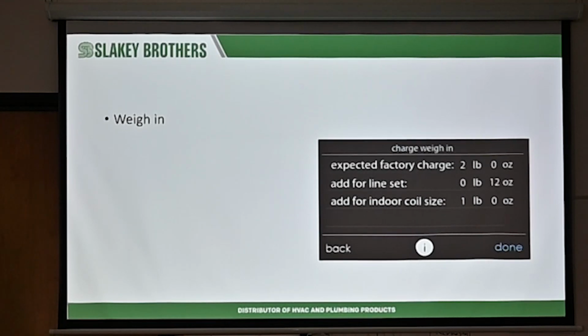That's really important. If you ever do a startup, and it could just be a 16-SEER 1-stage unit, regular old Bryant, and you add the right amount of weight to it per the line set, and you start it up, you're like, what the hell? My subcool is only 4 degrees, or only 5 degrees, and this says I need 10 or 12. Sometimes it's because of the evap coil.